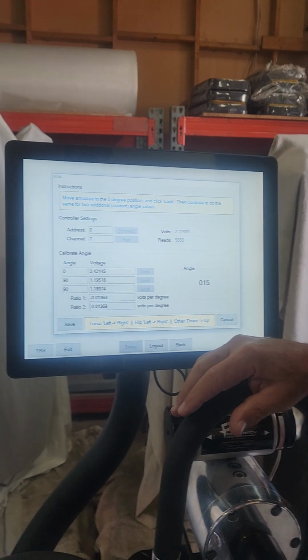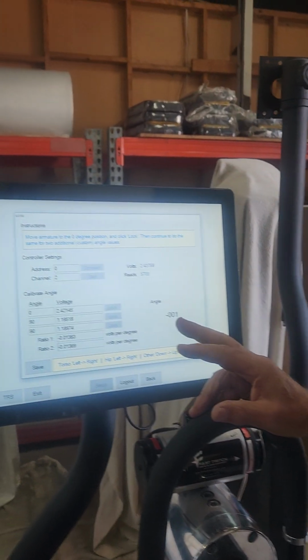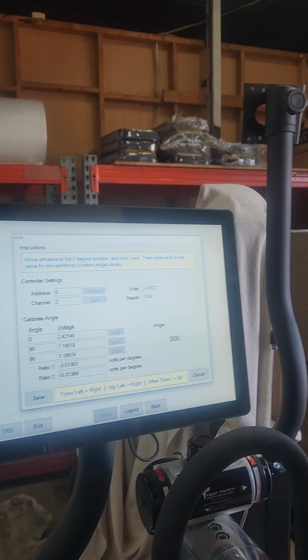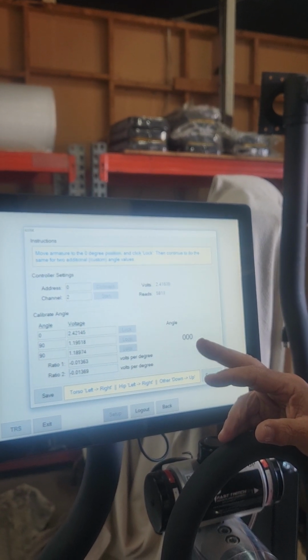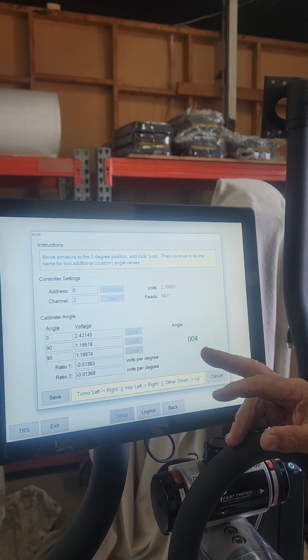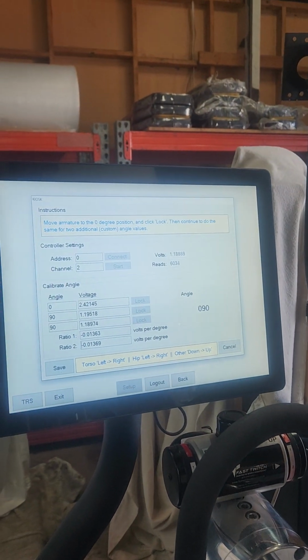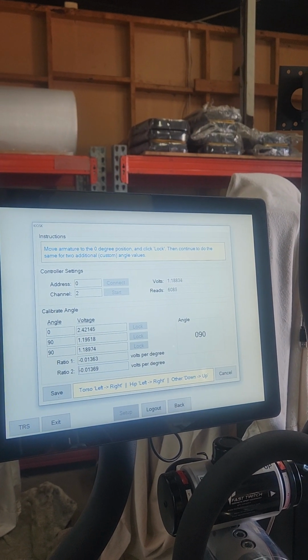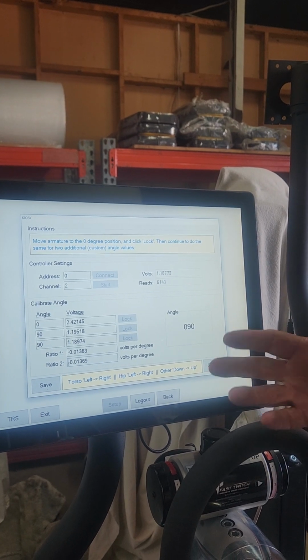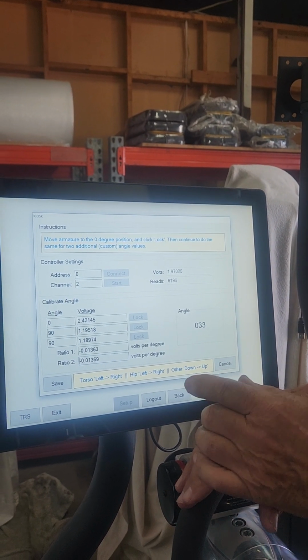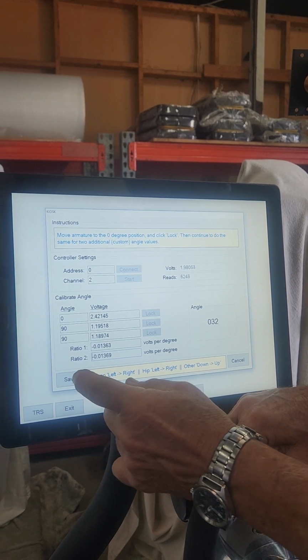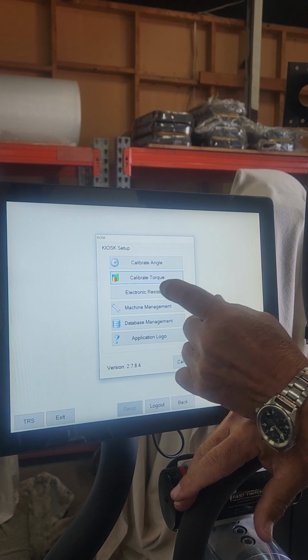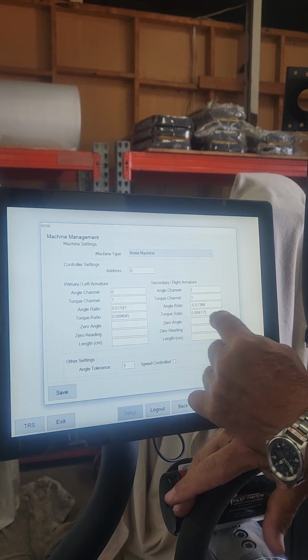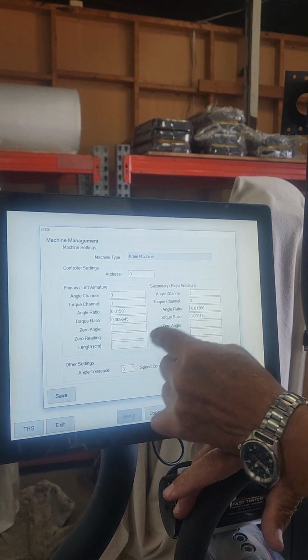Then the screen will show here, when I've got that in the perpendicular position, it's showing that it's exactly 0. It's right where it should be. Then when I'm moving this up to 90 degrees there, I can see that 90 degrees corresponds with my level there, so it's reading exactly right. And then from that position there, we just go save, and it saves that data to this machine management settings.